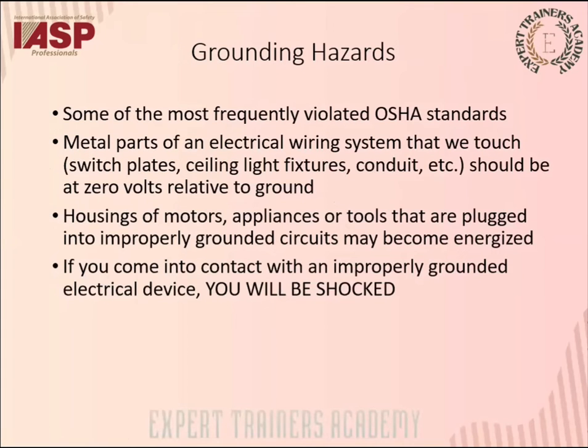Grounding hazard. This is among the most frequently violated OSHA standards. Metal parts of an electrical wiring system that we touch should be at 0 volts relative to ground. Housings of motors, appliances, or tools that are plugged into improperly grounded circuits may become energized. So if you come in contact with an improperly grounded electric device, you will be shocked. Generally, what are the electrical hazards we could see? We might see wires with no plug on them that are still put into the socket and used, or people carrying electrical tools and appliances by the wire. So these are other electrical hazards that we could see.